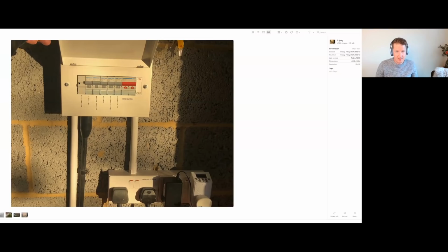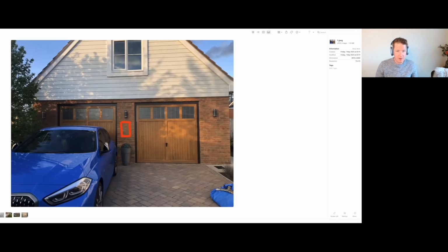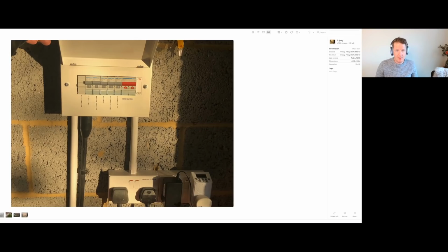But this is where the problem comes in, because if you look back at the photo, this garage is not just a garage - it's got a granny flat up above. So this garage consumer unit is feeding the sockets upstairs in the granny flat, and the sockets downstairs in the garage.